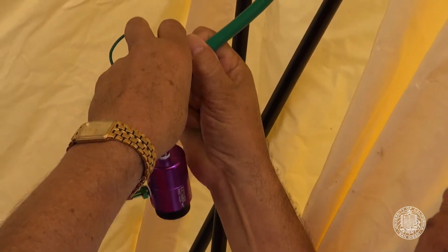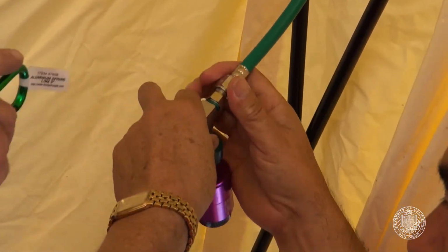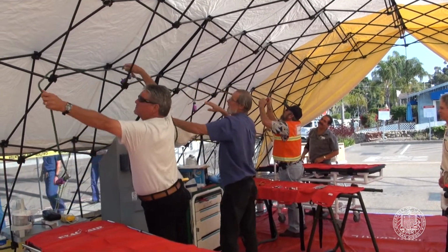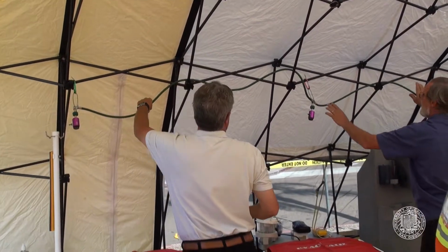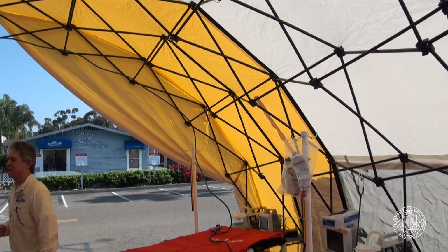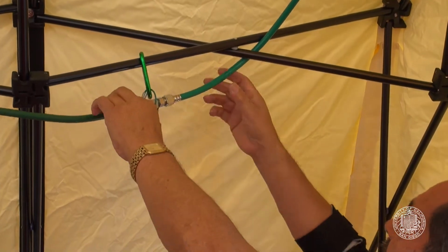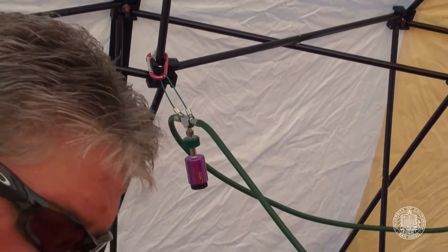The next thing to do is install the oxygen system. The oxygen system consists of an H cylinder of gas that's stored outside the tent and a single hose that runs around the perimeter of the tent with 10 individual flow meters. At the end of the tent, in the opening, at the archway, it's important that the oxygen system between flow meters number 5 and 6 go over the archway. The hose system can be either woven through the structure of the tent or attached with carabiners as shown here.